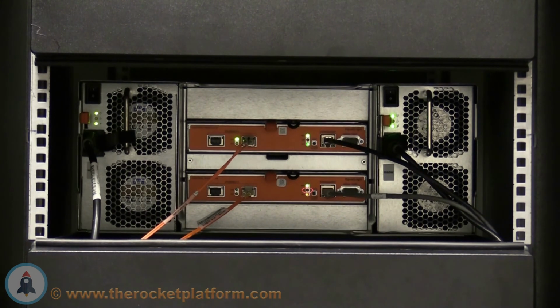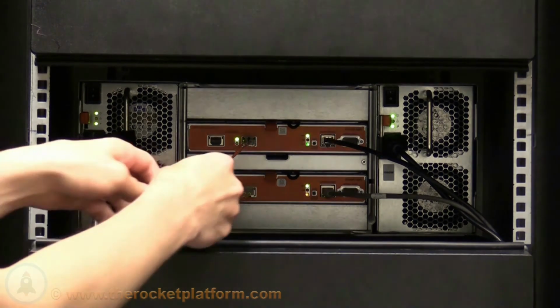The PWR light indicates whether or not the control module is receiving power. The ACT light indicates whether the controller is in the active, green, or secondary, amber. The ERR light will light up red to indicate an error within the controller during the boot process. Confirm the control module with default matches what is seen in the Controllers tab in the Group Manager.